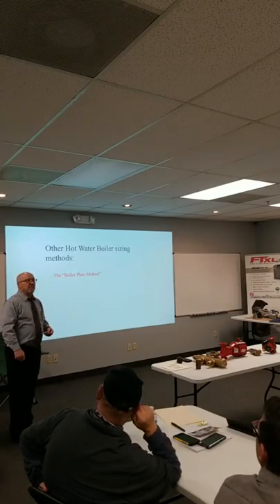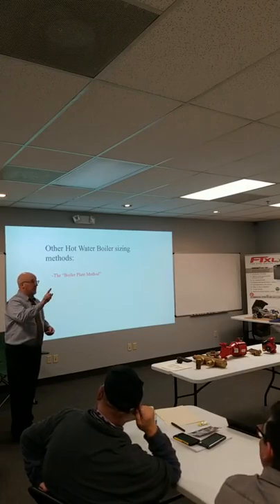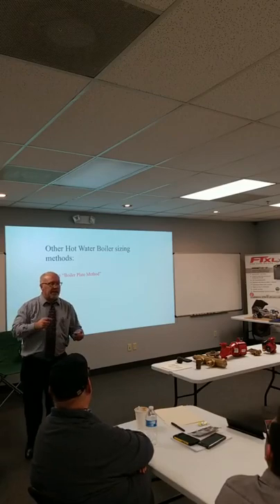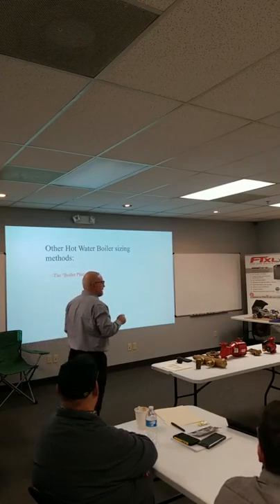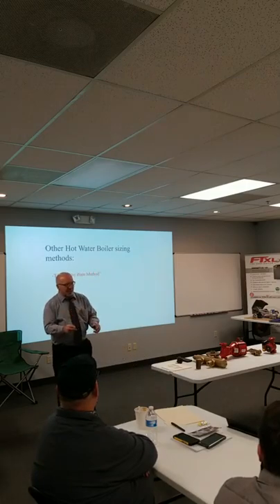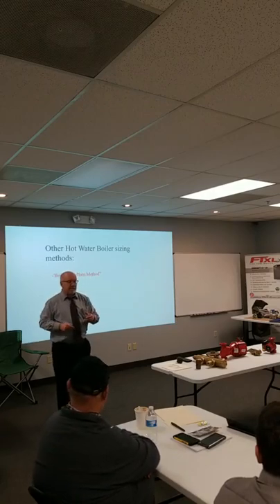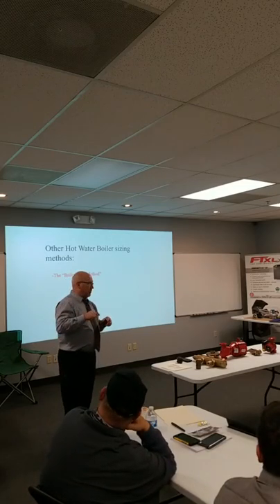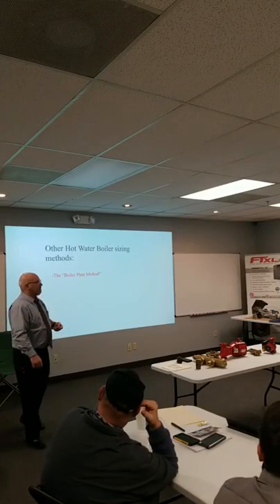See, if you oversize the boiler, then you just have to sell them a storage tank. And then you can trap all that heat there. So, buffer, or a buffer tank. Let's use the right terminology. But you're absolutely right. Putting in an oversized boiler, and that's what we do sometimes when they spend a lot of money on a condensing boiler and it's oversized, we got to go in and put a buffer tank in. So now we got this big volume of water that we're heating and we're storing it and we're waiting for those zones to call. Boiler may not have to come on, but that buffer tank may satisfy zones. We do that by design sometimes when we have small micro zones and we don't want to cycle the boiler every time it comes on, so we do a buffer tank. But that's great. Get that flywheel effect. Yeah.